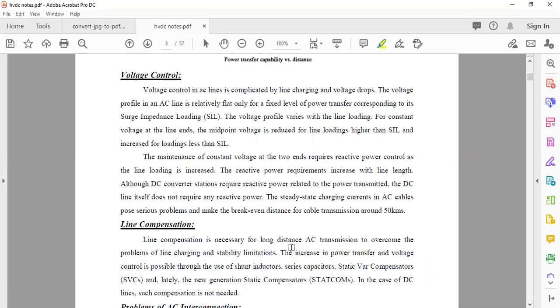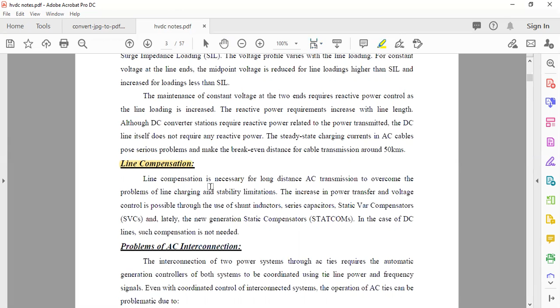Another factor to be considered is line compensation. Line compensation is necessary for long distance AC transmission systems to overcome the problems of line charging and stability limitations. For coping with that, the new generation static compensators, STATCOMs, are used. In case of DC lines, such compensation is not used. The cost of STATCOMs is pretty high as far as AC is concerned. In case of DC, no such STATCOMs are required.